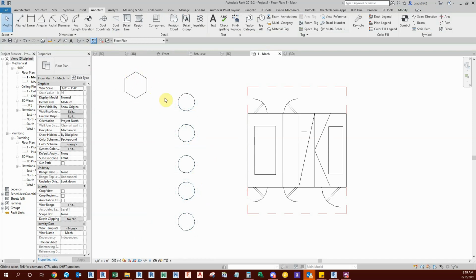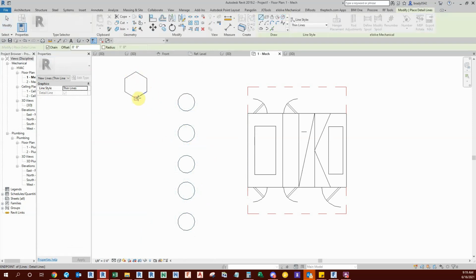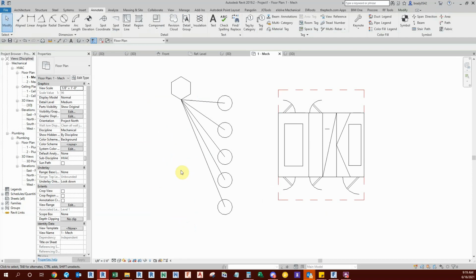So I'm calling my six-sided thing my source connector here, and then it will go connect to all of my target connectors. Depending on, like Eric, since you're a sheet metal guy, we'll use a sheet metal reference, like an air handler, for instance. Say you have an air handler here, and these are all VAVs. So your air handler would be your source, and the VAVs would be the target, and the air flows one direction always.